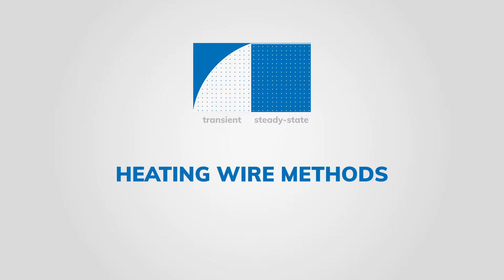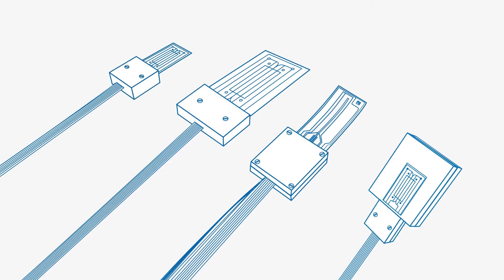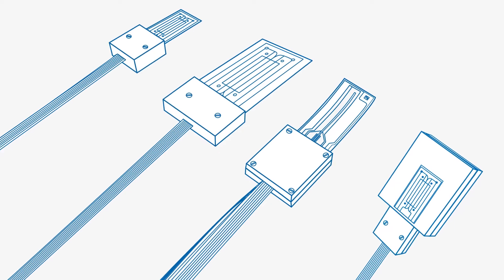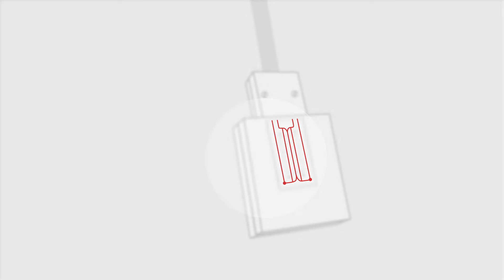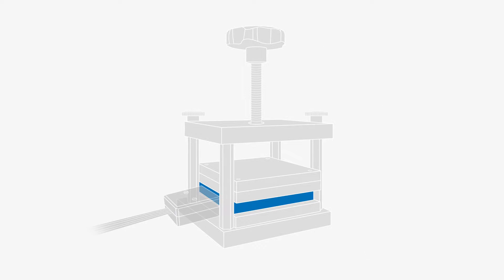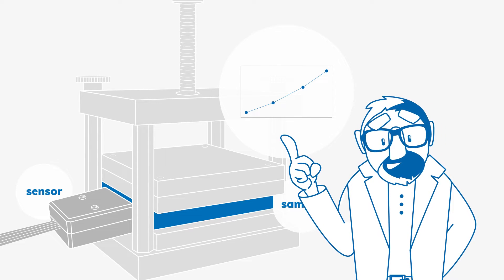Hot wire and heating strip methods are widely used – for example, in the transient hot bridge method – and also belong to the transient measurement methods. They can be found in various sensor configurations and offer the broadest possible range of applications and measurements. Embedded in a substrate, the heating wire emits a constant heat flux during the measurement, which causes a time-varying temperature distribution in the sample and the sensor itself. The temperature rise over time is measured by an integrated thermometer, from which the thermal transport properties of the material can be determined.